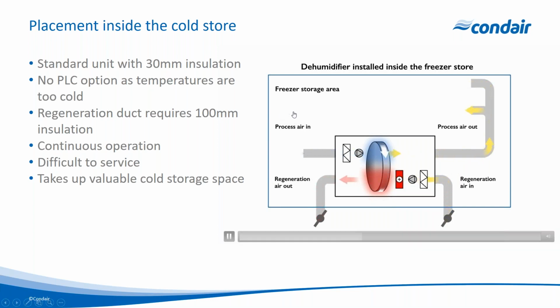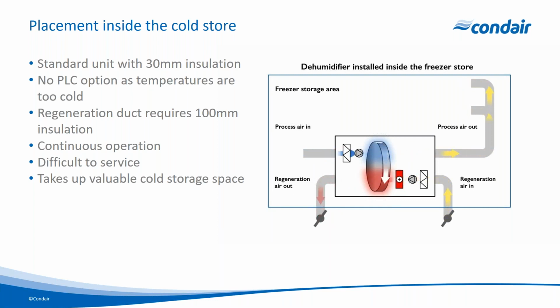Your regeneration duct does require 100mm insulation because you've got that warm, moist air that's still traveling out of the cold store. So we've got to make sure that we don't get heat transfer through either of those ducts. So we must have at least 100mm insulation. And it's got to operate continuously to make sure that it doesn't freeze up. And of course, it is in the freezer store, so it's difficult to service because it's -27, -28 degrees C. And really critically, it takes up valuable storage space within your freezer. And you're actually paying to keep that unit cold. You're cooling down that dehumidifier unit as well. But there are some other options.